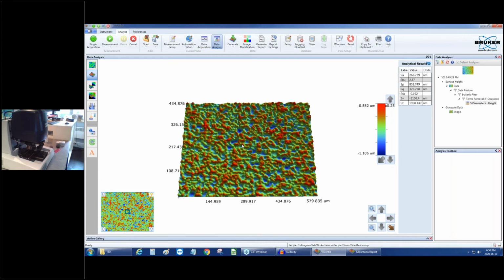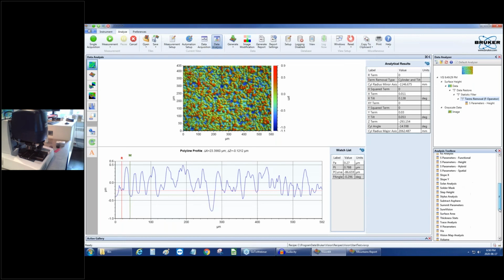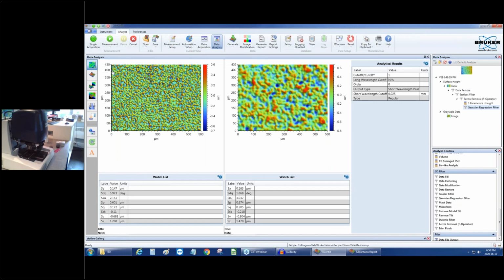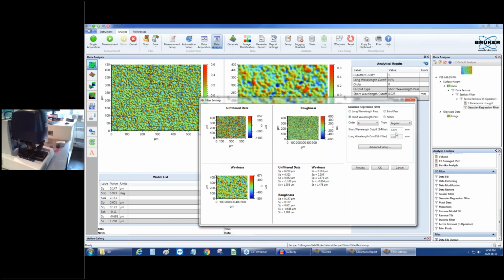So what I did is I used a lot of the spatial filtering through Gaussians, and this is what Don did as well to select different spatial things. And what I see is that the way to fine-tune the measurement is indeed to display what is high pass, so the roughness here on the left, and the waviness on the right side, which is the low pass. And here you can determine exactly what's happening, changing the cutoff.